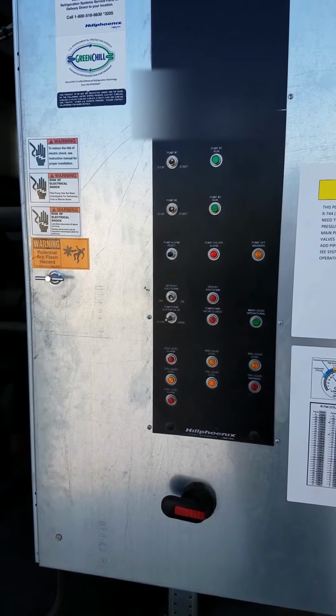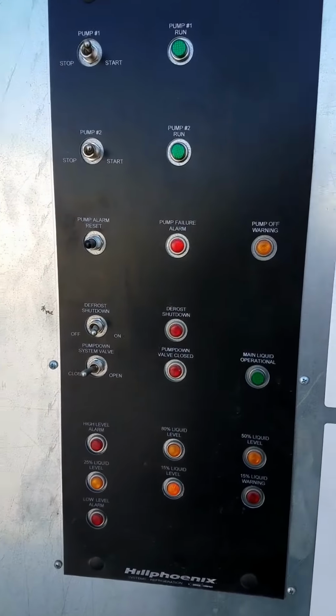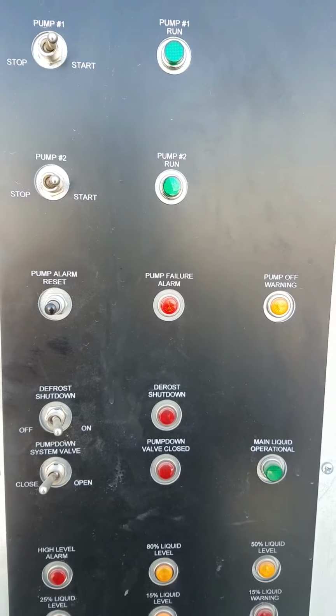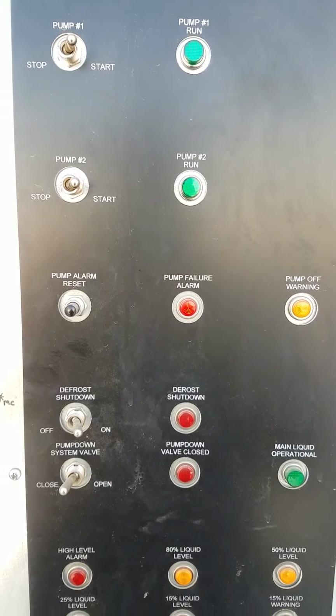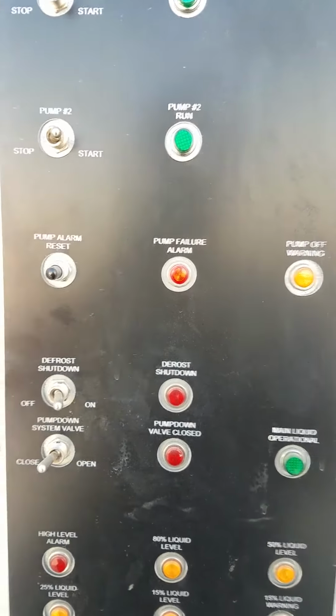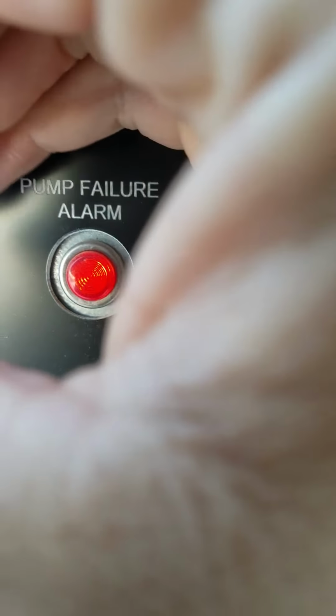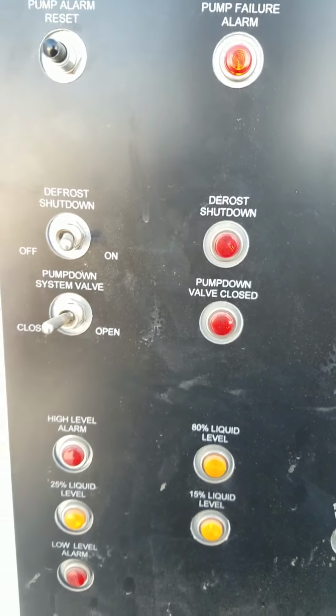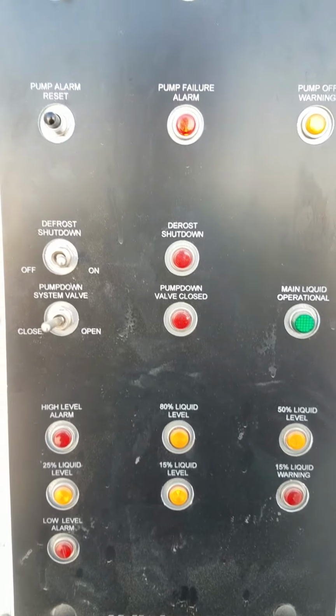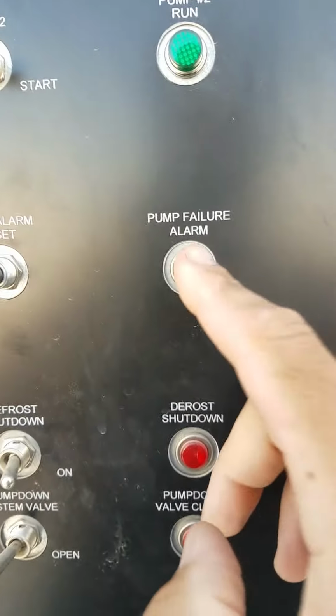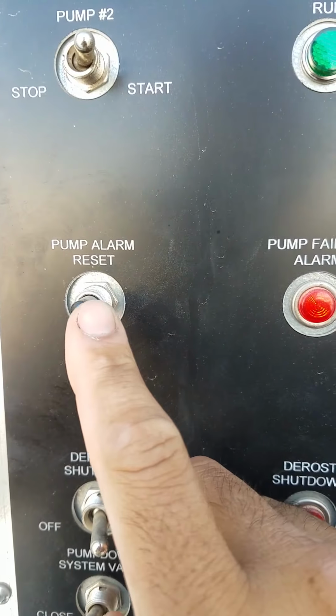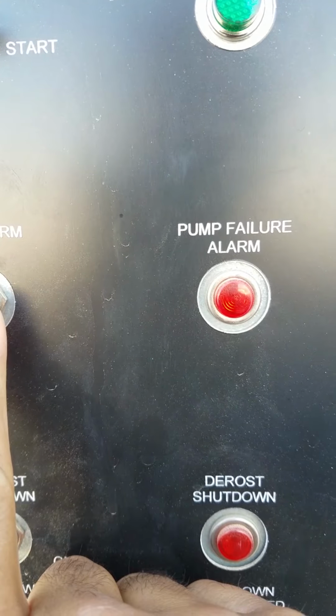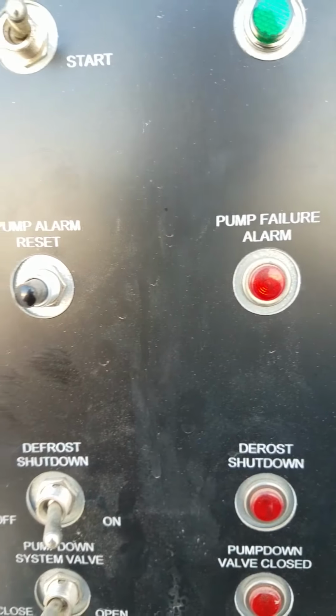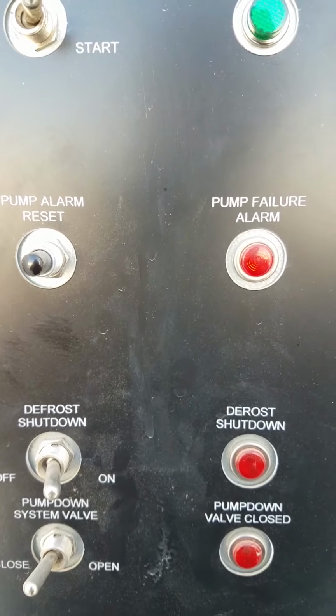Over here we got another panel that has the pumps. You got pump 1 run light, pump 2 run light, and I don't know if you can see that, but the light is on for pump failure. To get rid of that alarm, it's just a light. We're just going to hold this button down just to reset the light, and it goes away, you can tell. That's just to get rid of the light. Let's go see what happened.